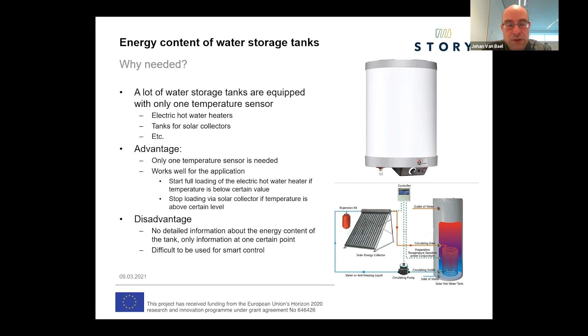For instance, electrical hot water heaters normally have just one sensor, used only to switch the electrical resistor on or off. It works perfectly, but the disadvantage is that you cannot use only one temperature sensor to know the energy content of the storage tank, because you measure the temperature only at a certain height and don't know the temperature above or below.